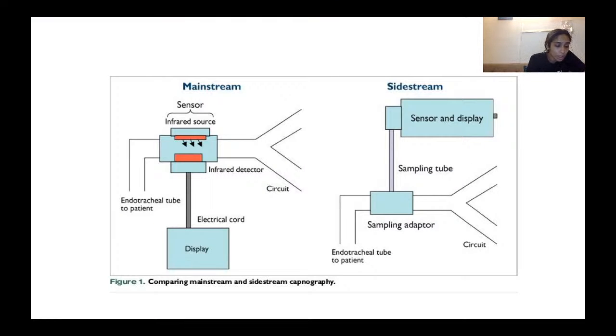However, some more advantages are, the mainstream has a faster response time. There's no delay time, like we discussed. No gas is removed from the breathing system, so no scavenging is required even with this. Water secretions are seldom a problem with this type of analyzer, although on the cuvette window there can be some secretions that can be cleaned. Then sample contamination by fresh gas is less likely. With the diverting monitor, sample contamination with fresh gas can occur. So with this side stream analyzer, there can be contamination with oxygen, which will decrease your EtCO2 curve basically.